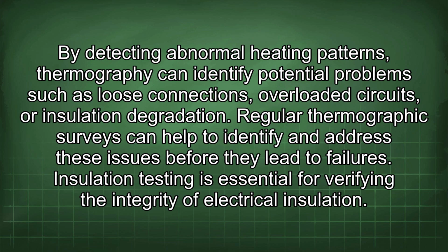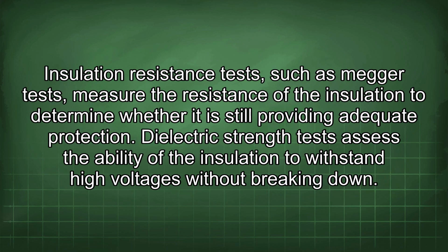Regular thermographic surveys can help to identify and address these issues before they lead to failures. Insulation testing is essential for verifying the integrity of electrical insulation. Insulation resistance tests, such as megger tests, measure the resistance of the insulation to determine whether it is still providing adequate protection. Dielectric strength tests assess the ability of the insulation to withstand high voltages without breaking down.